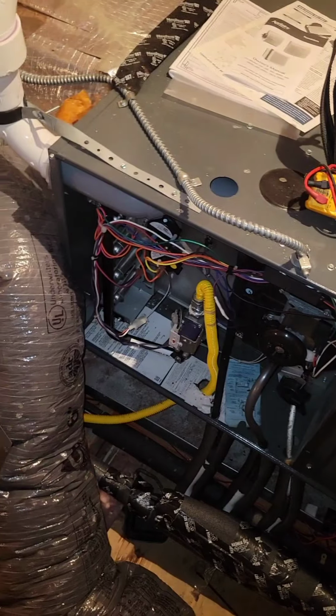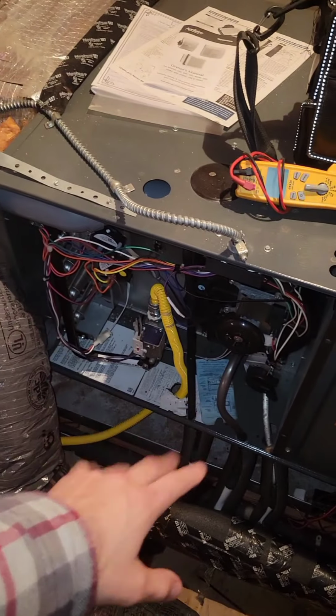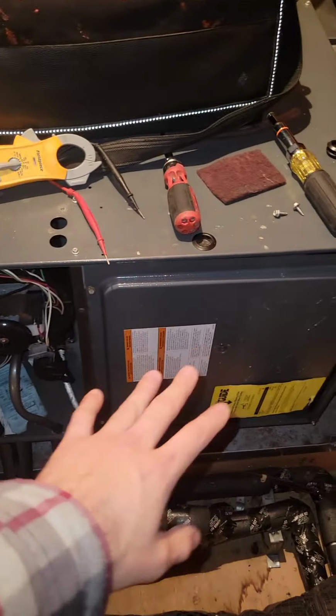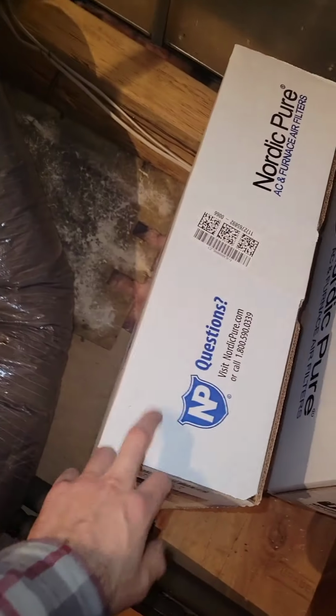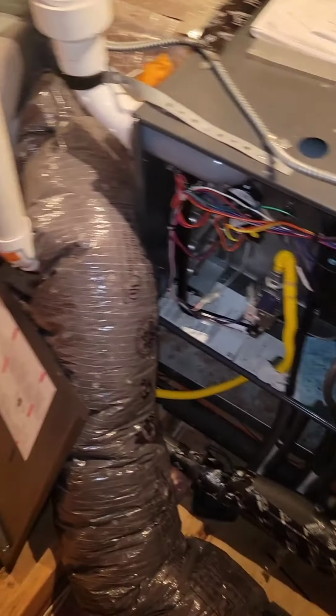Check gas lines, check all this other stuff, check all the safety switches here, make sure that all that's operational. Check the blower, amperage on the motors, both inducer and the blower motor, and we'll change the filters and make sure that they're good to go.